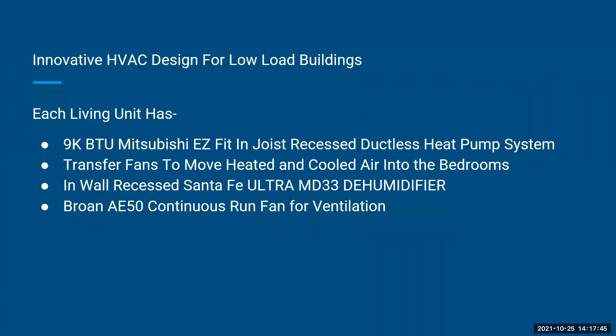Once we solved that problem, we still needed to get air into the closed door rooms, being the bedrooms. So we used in-wall transfer fans that transfer air from room to room without having to run ductwork into each room. This is an innovative HVAC design strategy mostly used in passive home, but we've been able to apply it to LEED buildings and other low load homes that don't meet passive standard but still have tight enough structures that you don't have to worry about air getting pulled away by some in-home current, which happens in looser buildings that aren't built as tight.